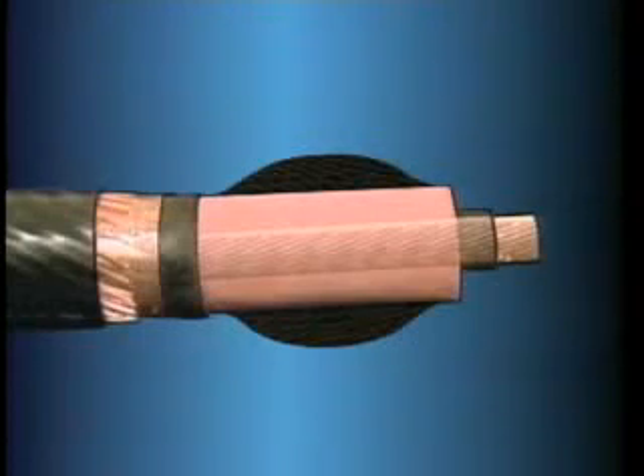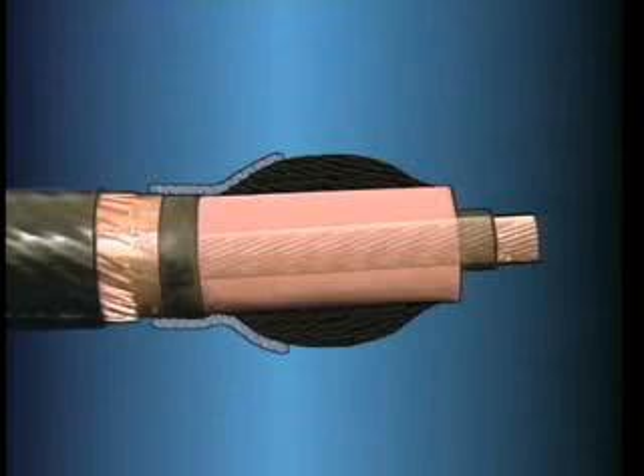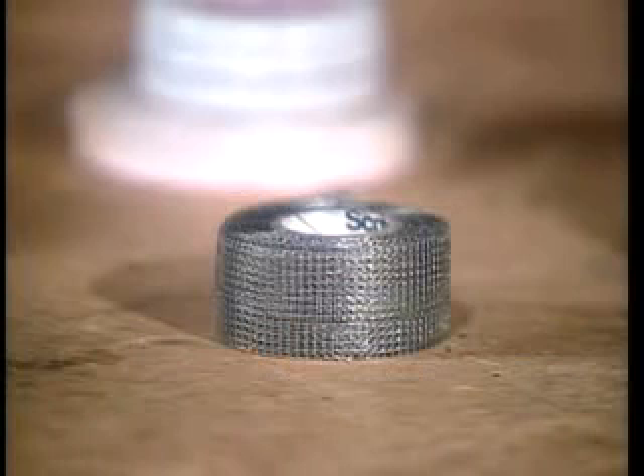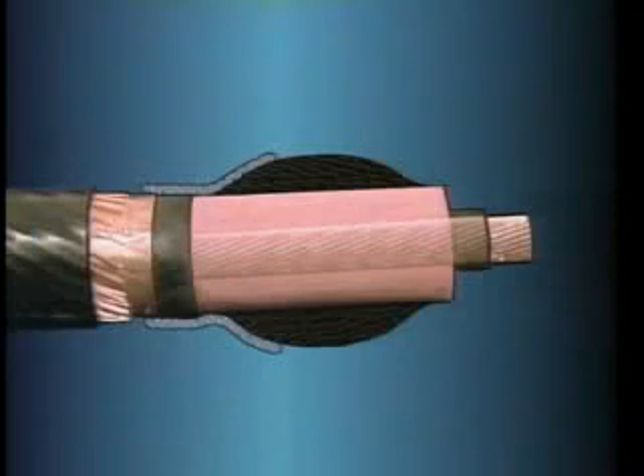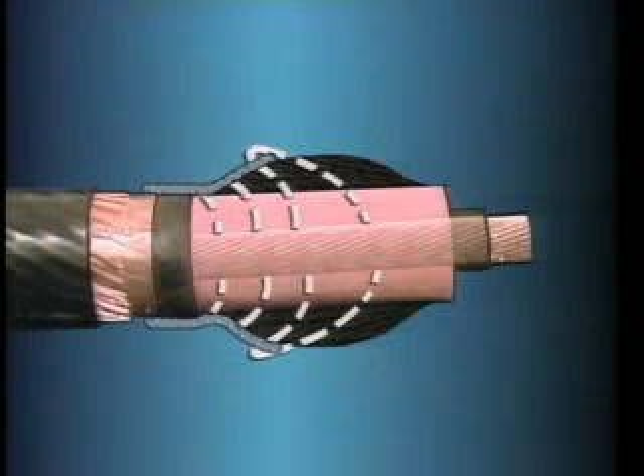After the insulating material is added to increase the thickness of the cable insulation, the insulation shield is extended up the stress relief cone to just before the high point of the cone. The material used to extend the insulation shield is usually a semiconductive tape or a metallic braid, as shown here, or both. Increasing the insulation and extending the insulation shield spreads out the voltage stress over a larger area so that it's not concentrated at any given point.